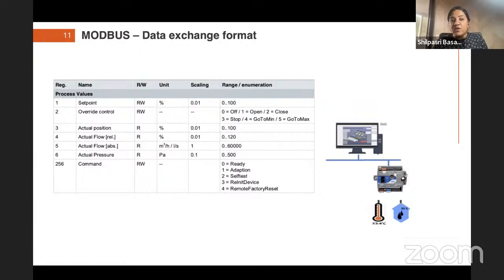Ideally, to understand this on an equipment, a person needs access to the manual for that equipment. If there was an upgrade, I had to have access to the upgraded manual. If I had a previous manual and my equipment had a different version of Modbus exposed, I'd find errors, or while configuring and reading it, there would be mismatches we'd need to figure out, working out which version mapped to which manual. So that's how the data was with respect to Modbus.